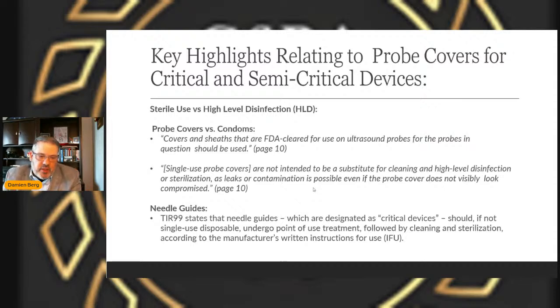You just don't know what's going to be used. That's when we talked about needle guides, because needle guides are very interesting since they are now critical. Most probes are considered semi-critical devices, so according to Spaulding, they do not need sterilization. But once it goes into puncturing the skin, it does now require sterilization. So those of us who process these need to know how they're going to be used, and that's where probe covers and sterile covers really come into account. If you're processing these in your facility, work with your clinician partners and know how they're using them in procedures. That's what that is about, and again, it's in the IFUs and also in this document.